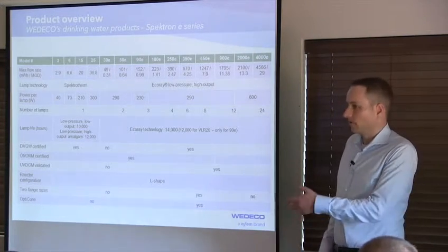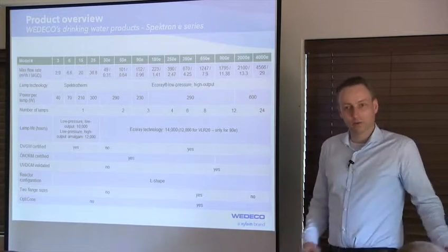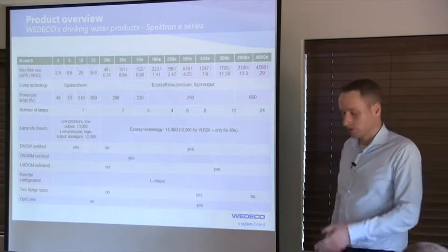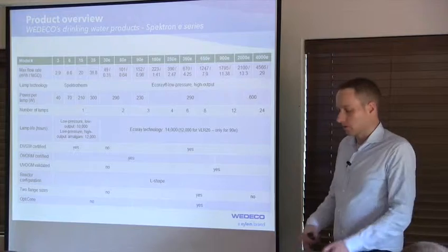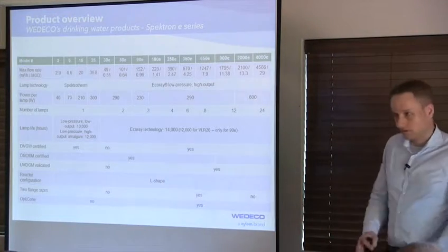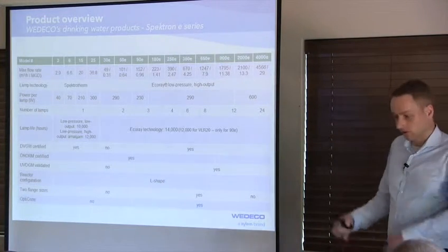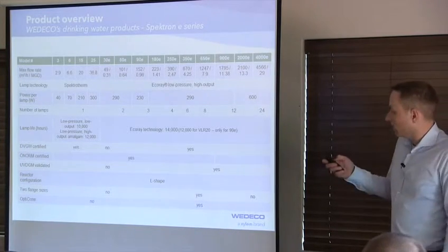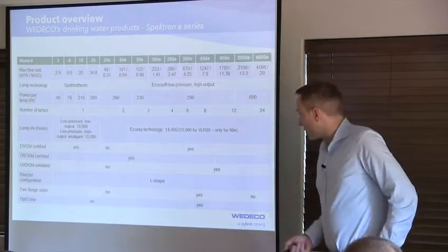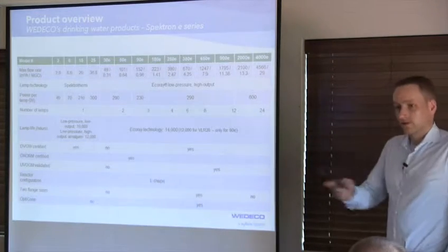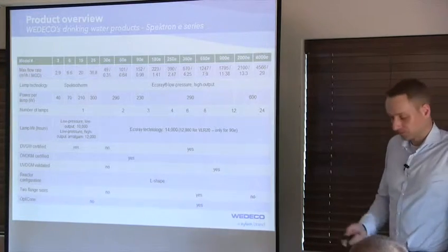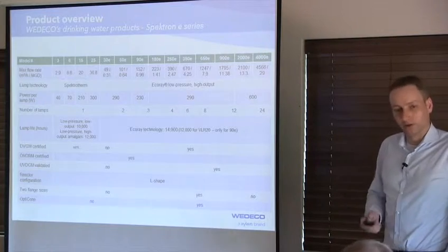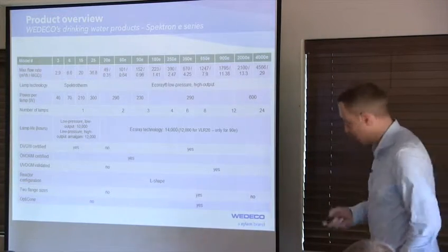On a UVT of 50%, calculated with the standard theoretical approach, it is something completely different from 30 millijoules at a different UVT. So you don't know what your performance is, and with these certified and validated systems, they are tested over a huge range of points, and you know actually what you can really do with your system.